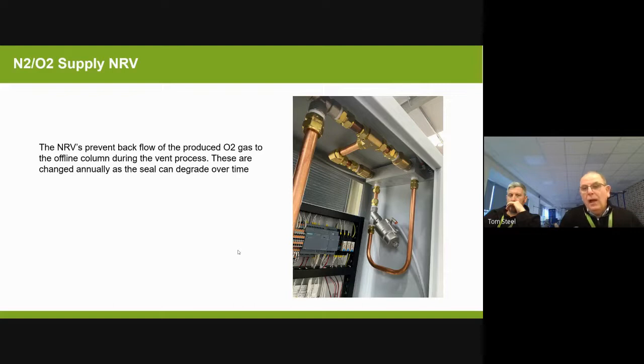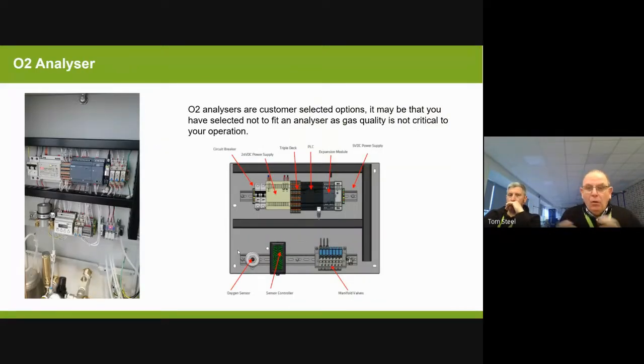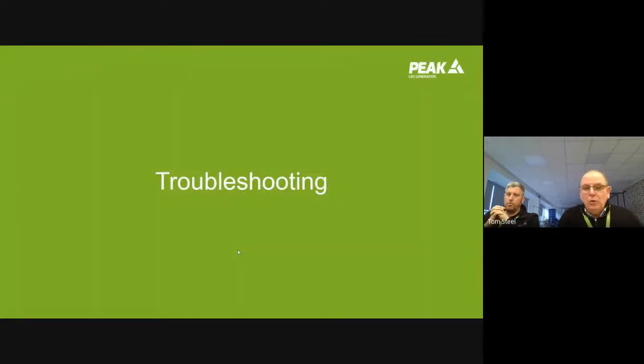And if it's doing that, consider the amount of workload on each NRV, shuttling back and forward as we take the air and the oxygen, and we pass it through these non-return valves. So they do wear and they do need replaced. Oxygen analyzer, we said every 24 months before we would actually repair the oxygen analyzer. So we are actually going to move on to the troubleshooting section of this.